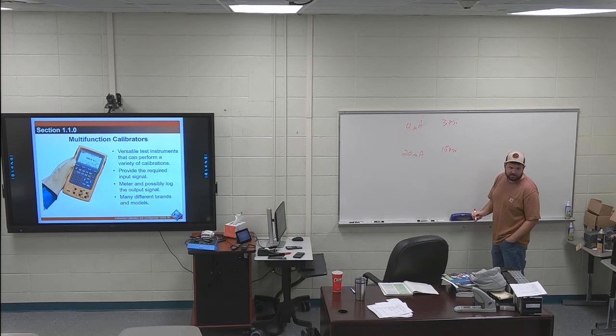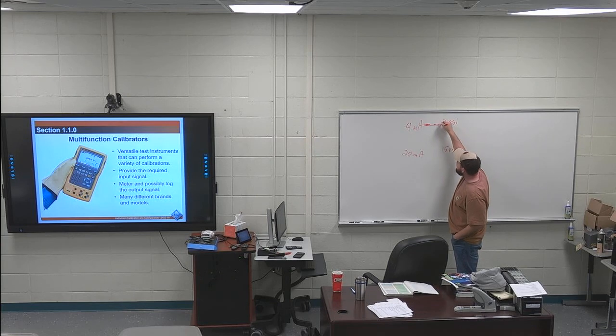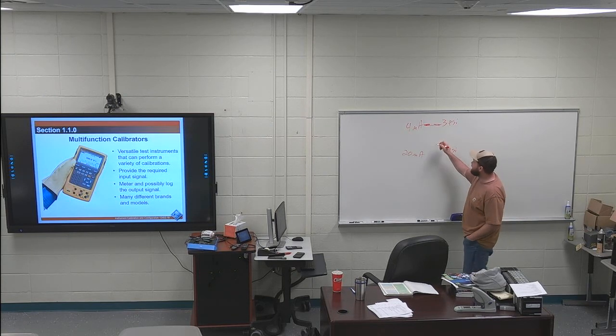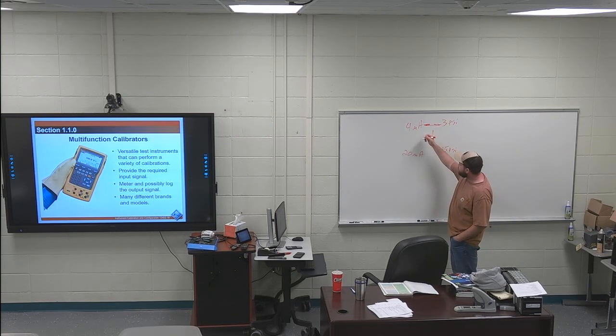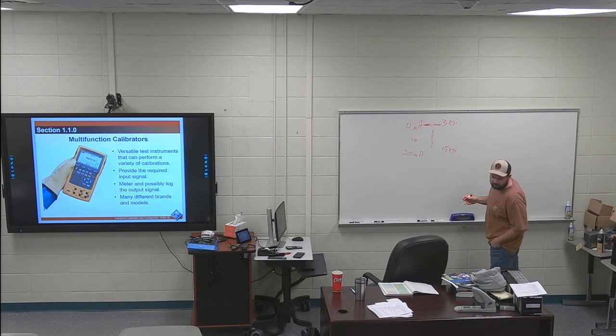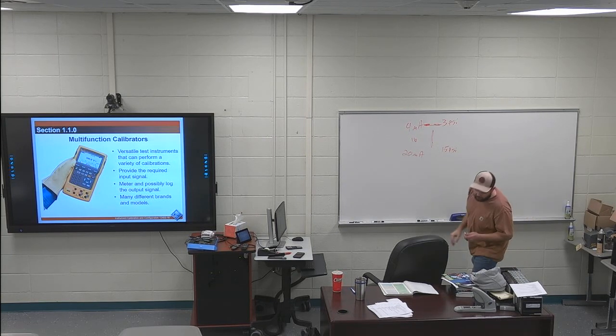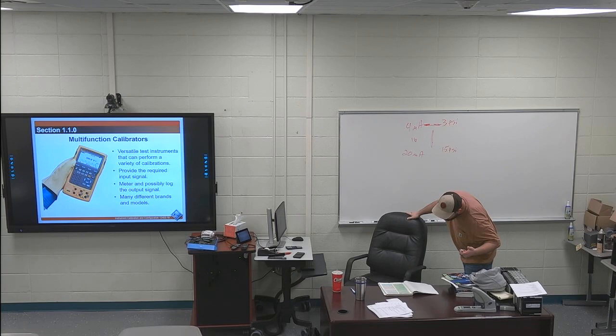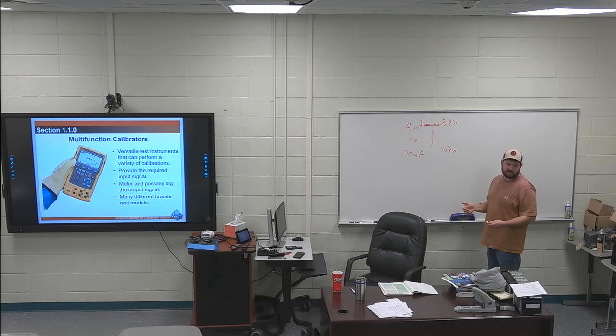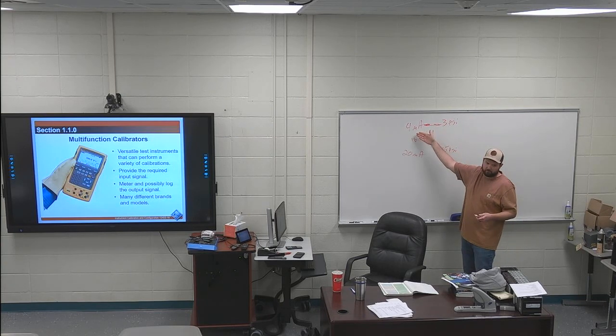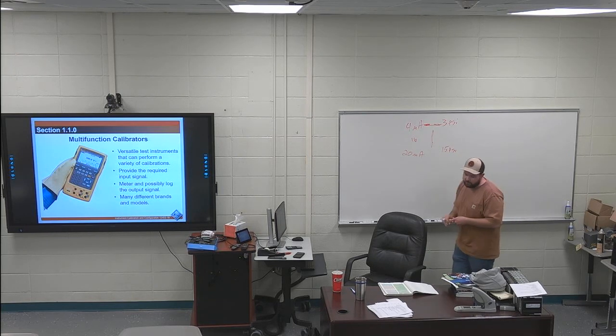So calibration is making sure that whenever I'm at 4 milliamps, I'm at 3 PSI. When I'm at 20 milliamps, I'm putting out 15 PSI and everything in between, right? So whenever you're at like 16, you're at whatever you're supposed to be. A lot of times you'll do what's called a zero and span calibration, which is your most basic type of calibration, where you do the zero, because this is our 0 for our air, and then this is 100%. So that's zero and span. You also have 3-point calibration and 5-point calibration.